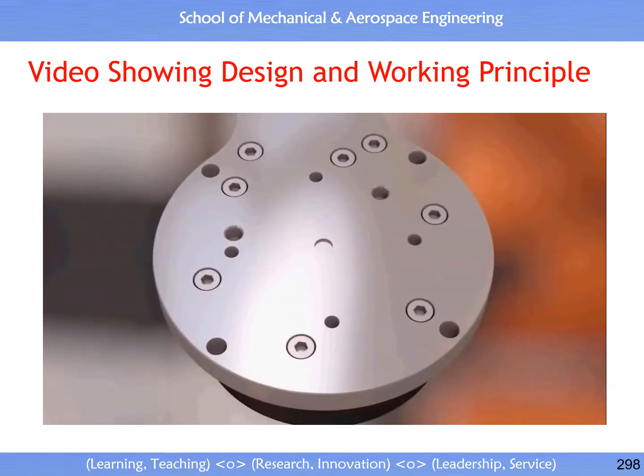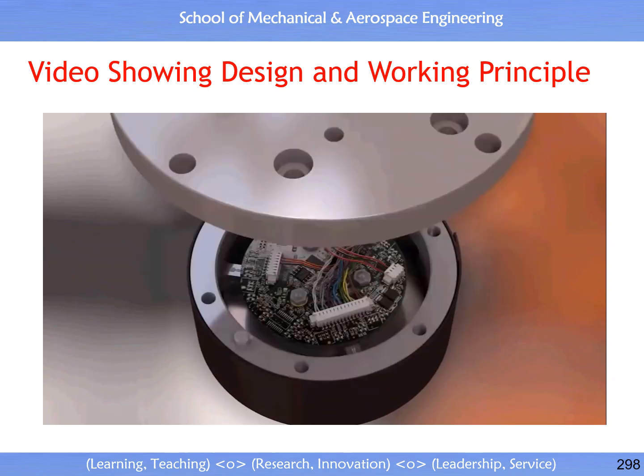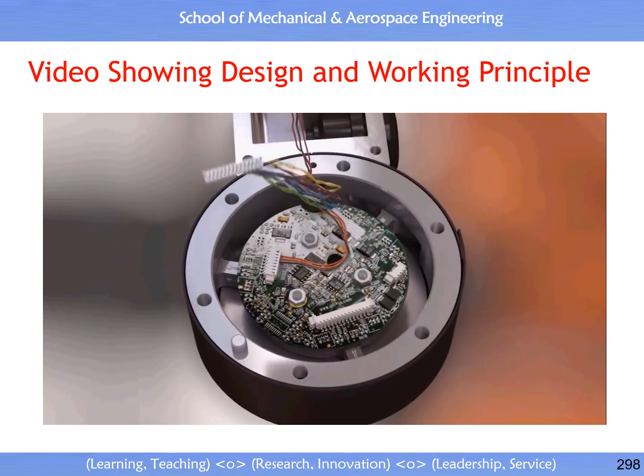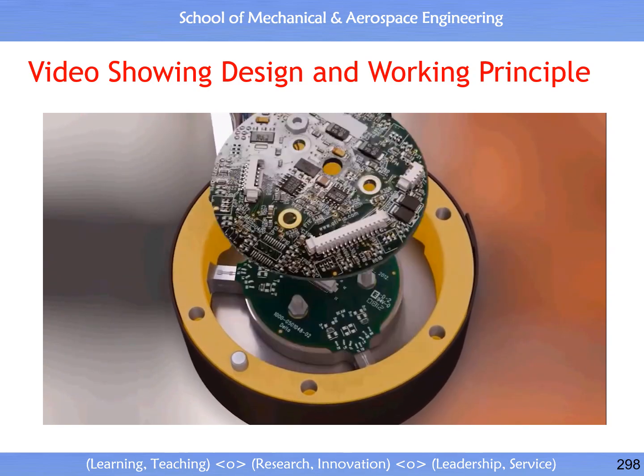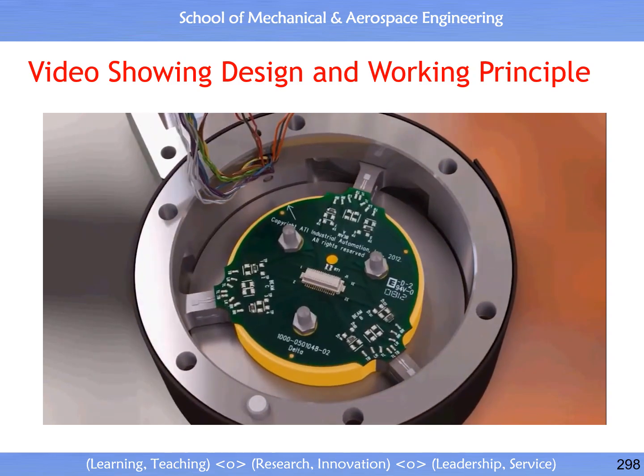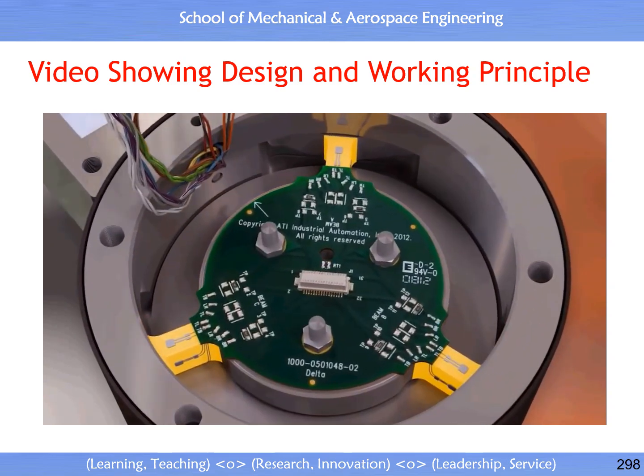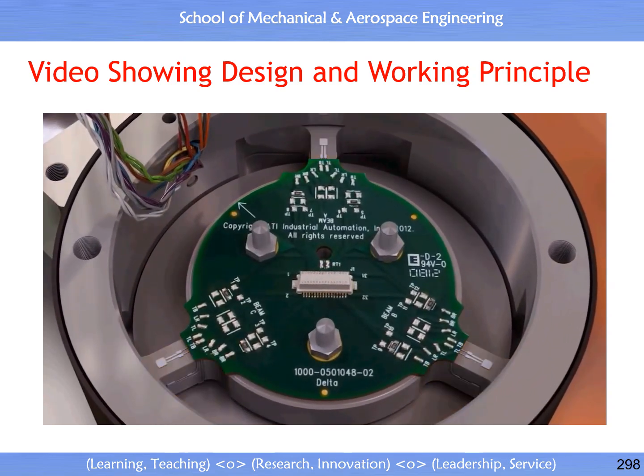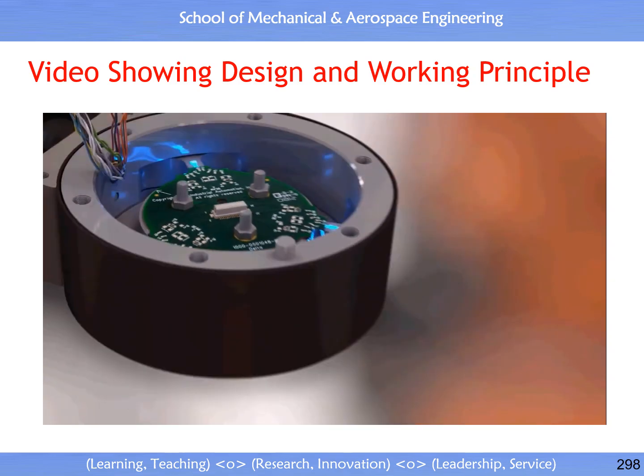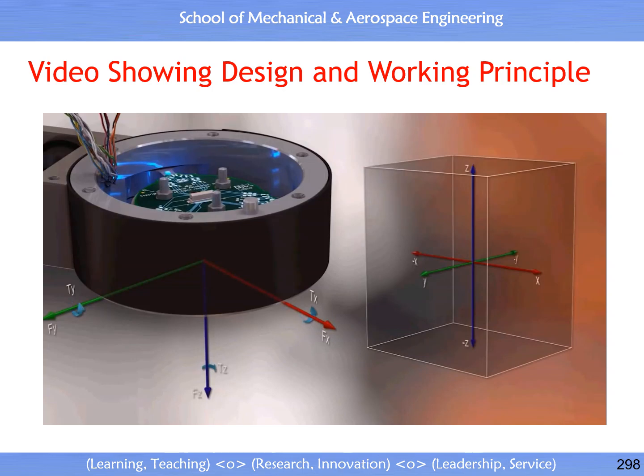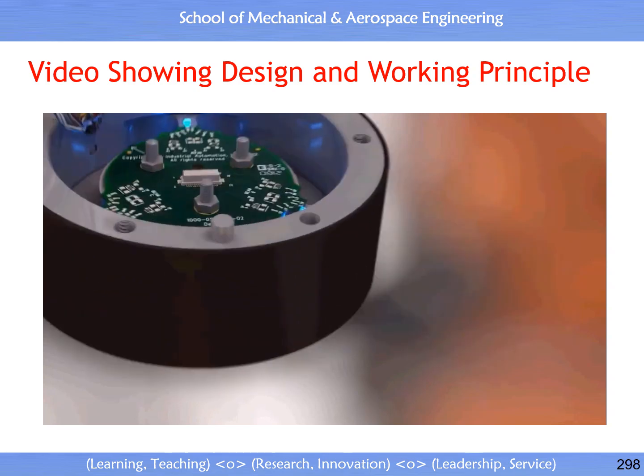When you look inside the ATI force torque sensor, you can imagine it resembles a wheel with an outer wall, with an inner hub, with spokes or beams connecting them. Each beam has 4 silicon strain gauges that function in pairs to form half bridges. The output of the transducer is 6 channels of strain gauge voltages. The output is digitized and then converted to force and torques through a matrix calculation.